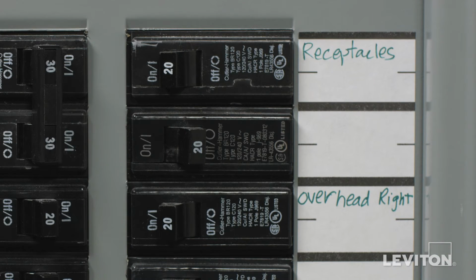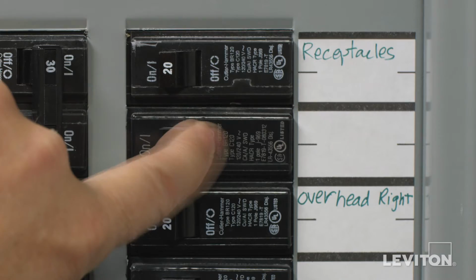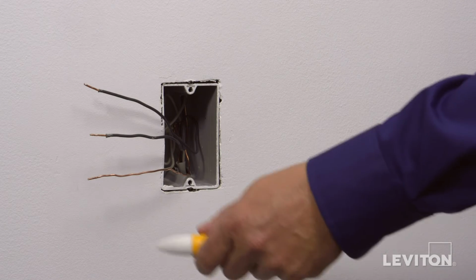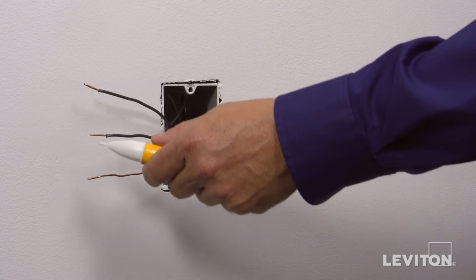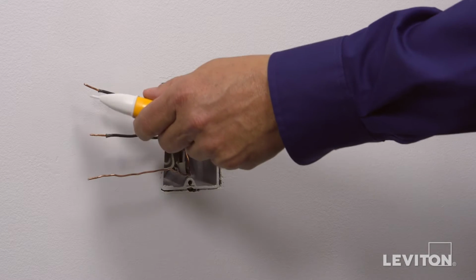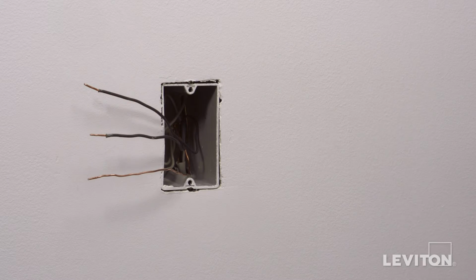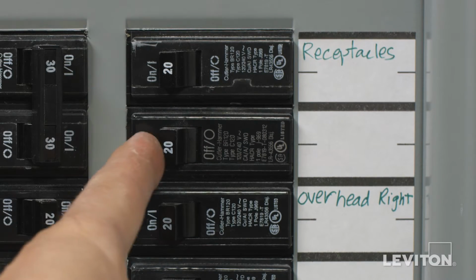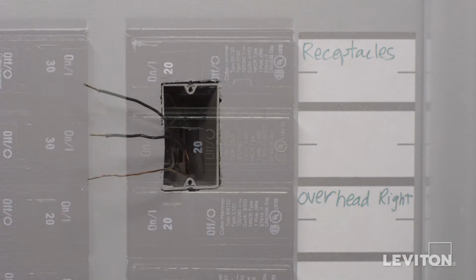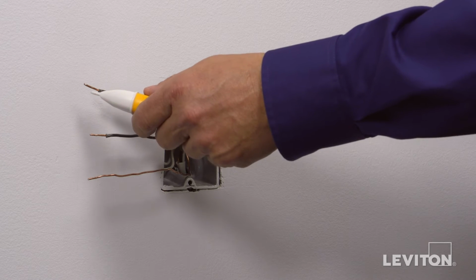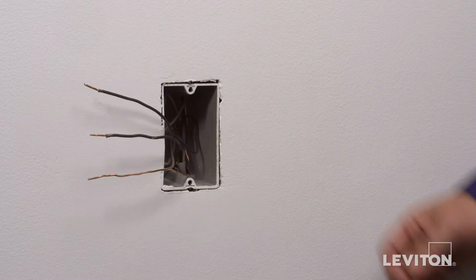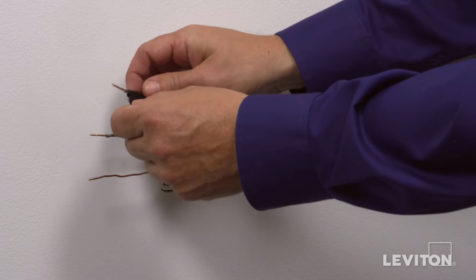Now, we need to identify the hot wire. To do this, turn the circuit breaker back on. Carefully use the voltage tester to test each wire. The hot wire will be indicated by the tester. Once identified, turn off the circuit breaker to shut power and test to ensure that the power is off. Use a small piece of electrical tape to label the hot wire.